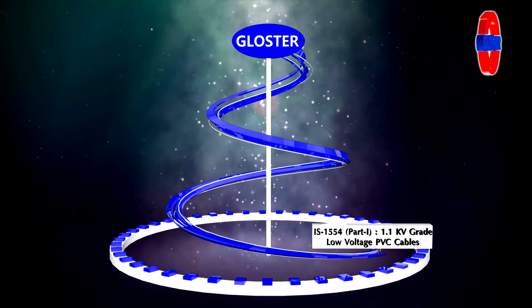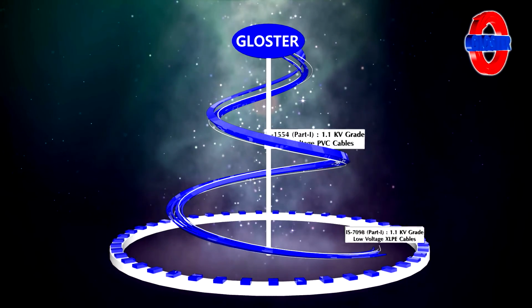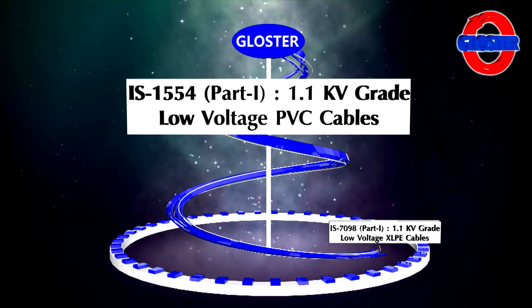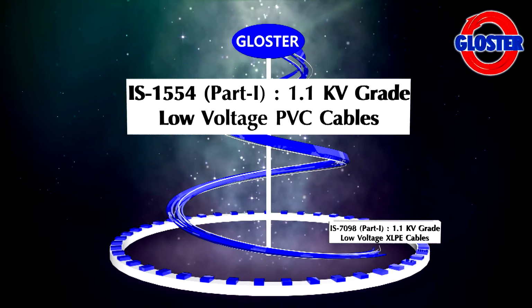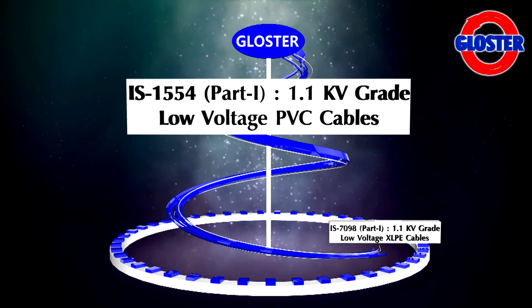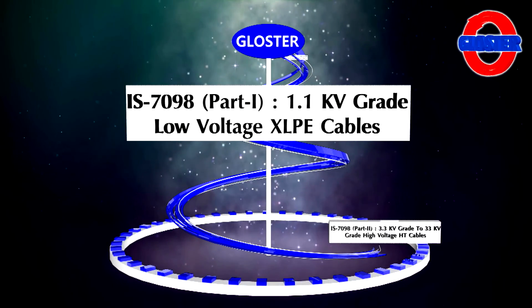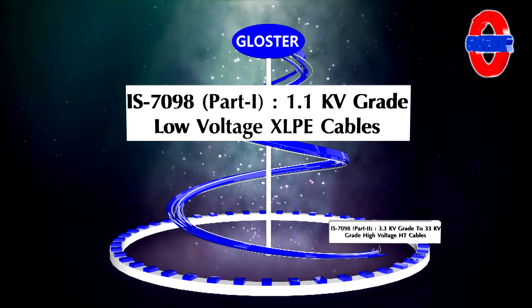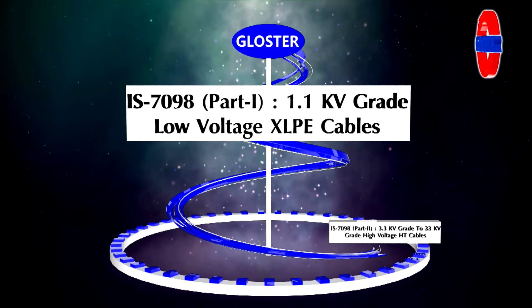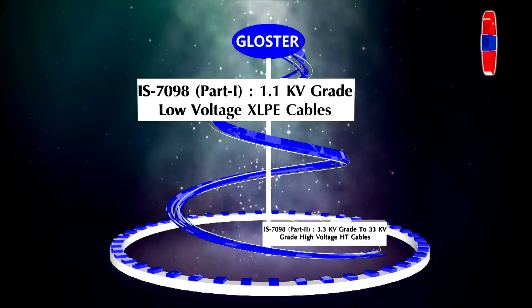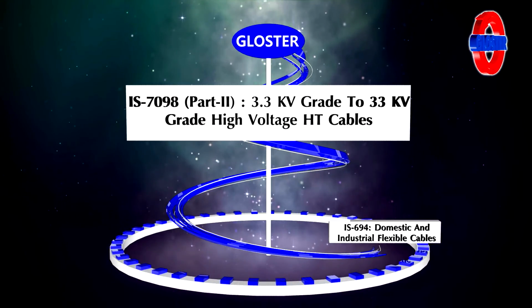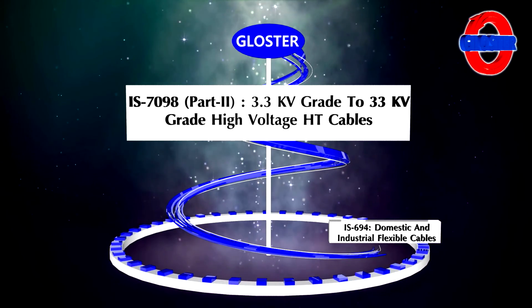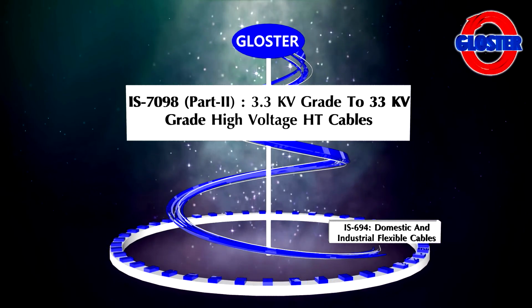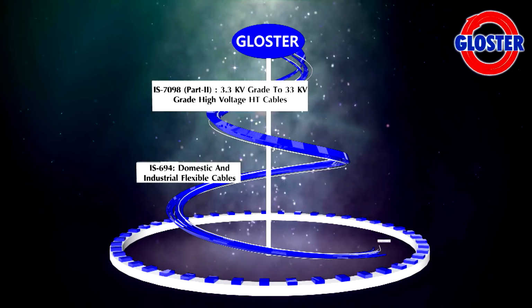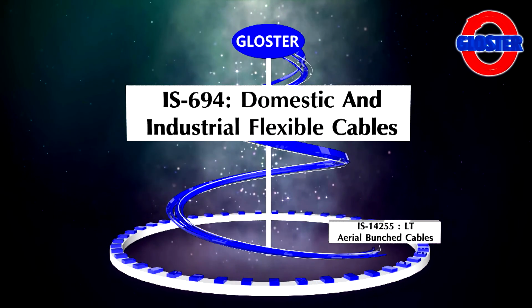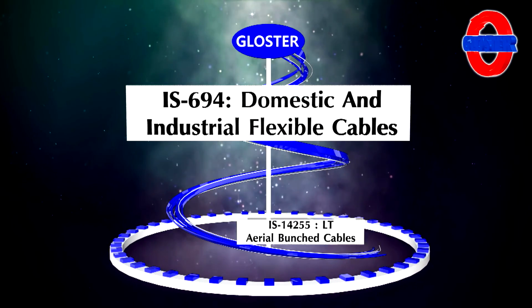Cables are manufactured as per relevant IS and international specifications. IS 1554 Part 1, 1.1 kV grade low voltage PVC cables. IS 7098 Part 1, 1.1 kV grade low voltage XLPE cables. IS 7098 Part 2, 3.3 kV grade to 33 kV grade high voltage HT cables. IS 694 domestic and industrial flexible cables.